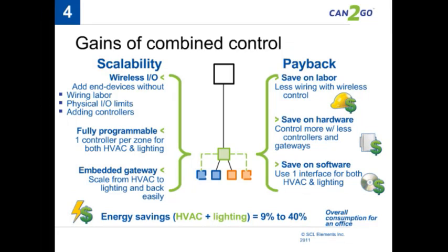When we look at the gains of combined control, there's a couple. From a scalability point of view, with wireless IOs you can add end devices without wiring labor. There's no downtime - I just stick the wireless sensor on the wall and you're up and running. It gets automatically configured into your system, and you can start using that CO2 sensor, for example. It's fully programmable, one controller per zone, so it can be used for both HVAC and lighting or window blinds. And the embedded gateway means everything is built into the controller.